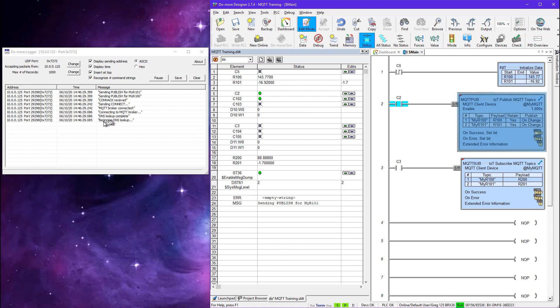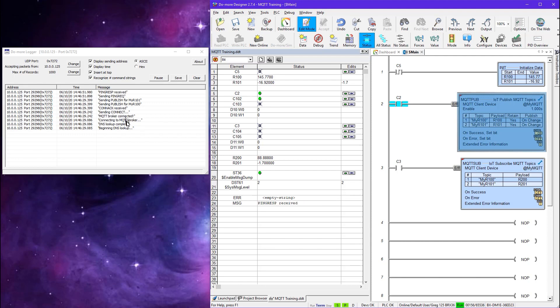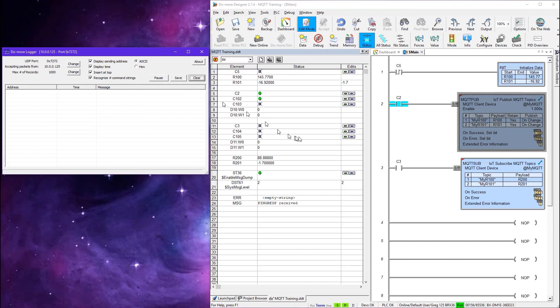Here you can see these messages that are being sent and being captured by Do-more Logger. So here you can see that the first thing that happened was he looked up that DNS or the URL of my broker which is on the internet. He looked that up and found it. That's what that is. So he queried the DNS on our network and he found it. Then he connected to the broker. The broker responded. These are the connection and connection acknowledge. And then there was the publishing of the two topics. And since I've been sitting here talking he's had to ping him because of the keep alive time.